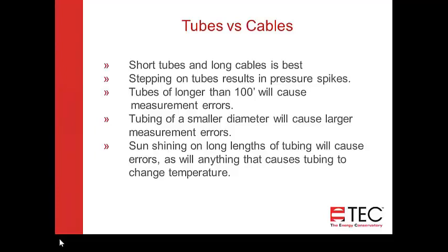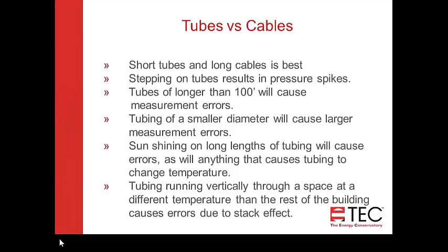If there's a temperature change somewhere along the length of tubing caused by the sun or something else, that can cause fluctuations. If you're running tubing through a vertical space at a different temperature — for example, running it outside and back inside the building — that tubing will be at a different temperature outside and you'll get fluctuations in pressures caused by that temperature difference. So it's not advisable to run tubing through a space that's at a different temperature. Wherever you can, use short tubes and long cables.